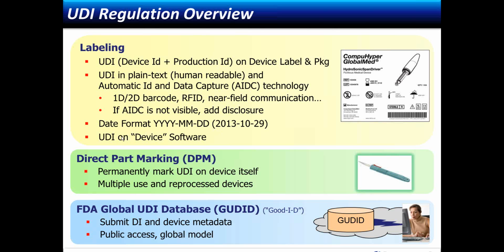One last topic on labeling. UDI does need to be applied to standalone software that is considered a device. So in the event the software is shipped out as a physical package, then there are certainly UDI markings on the package carton, as well as identification of this particular piece of software in the about page of that software. If it's a downloaded piece of software, then obviously the package is not there. The AIDC requirement is removed, and the presentation in this case would simply be the UDI in the about page of that piece of software.